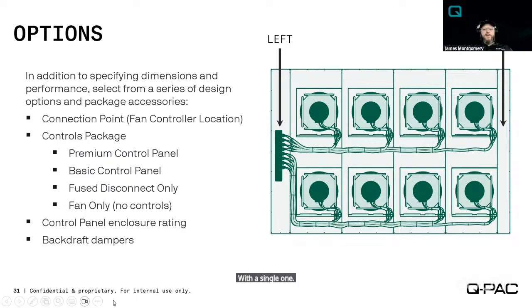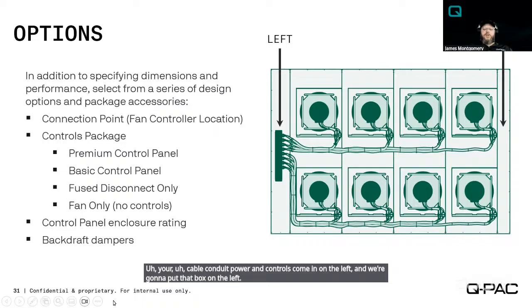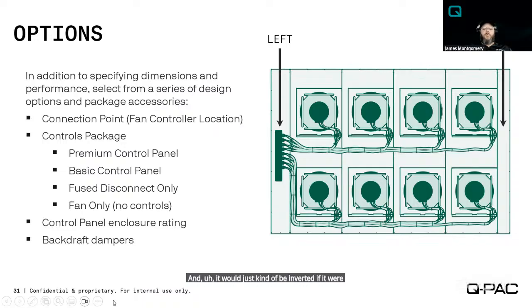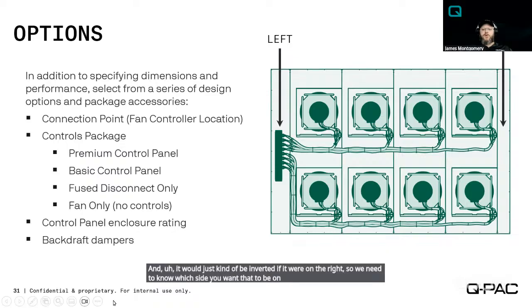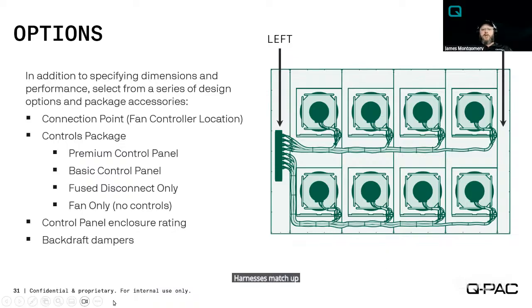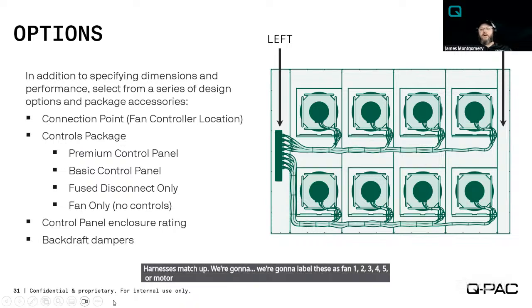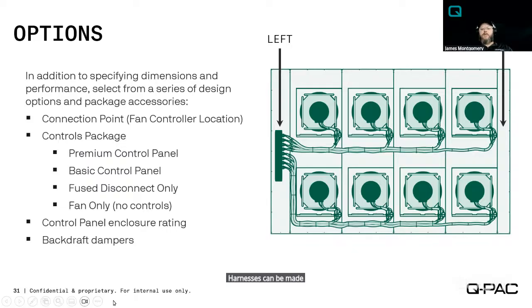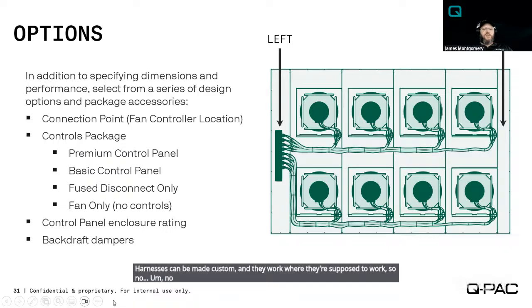So options, I was talking about that left or right. Your cable conduit, power and controls come in on the left, and we're going to put that box on the left, and it would just kind of be inverted if it were on the right. So we need to know which side you want that to be on. So all of those harnesses match up. We're going to label these as fan 1, 2, 3, 4, 5, or motor 1, 2, 3, 4, 5, 6, 7, 8, or whatever. And we need to know where those are going to be. That way, each one of those harnesses can be made custom, and they work where they're supposed to work. So no surprises during an installation.